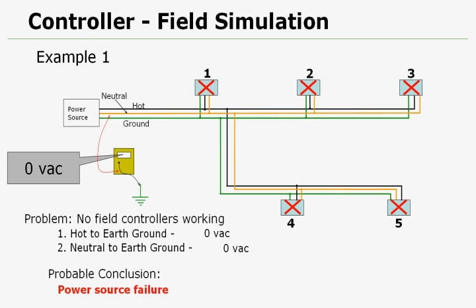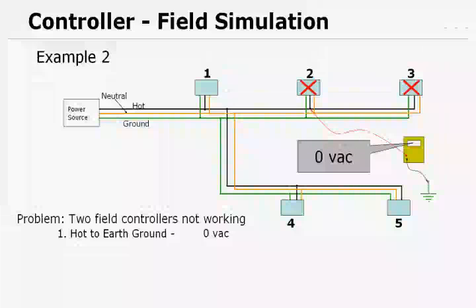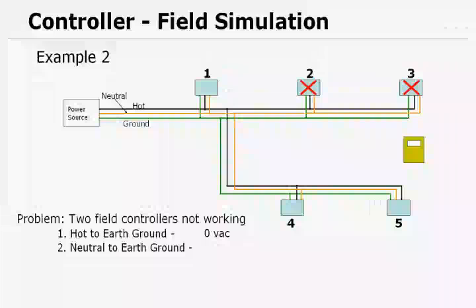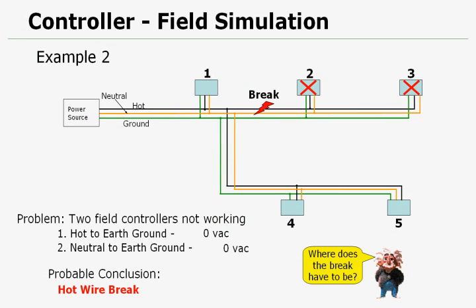Here's example two. Out of the five controllers, two are not working. So first let's take our readings hot to earth ground. We're going to do this at the first controller that's not working from our power source. Here we have 0 volts. Let's take a second reading, neutral to earth ground. And here we have 0 volts. Well from what we've learned so far, there's got to be a break. Where does the break have to be? We can deduce that it's a hot wire break. And it has to be right before or between the first controller that's not working and the last controller that is working.